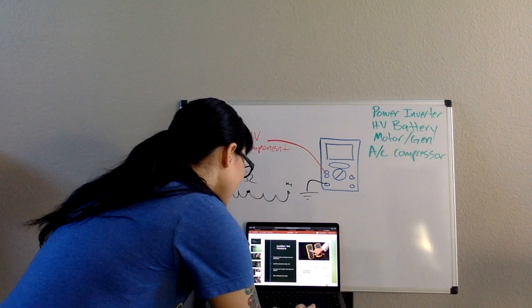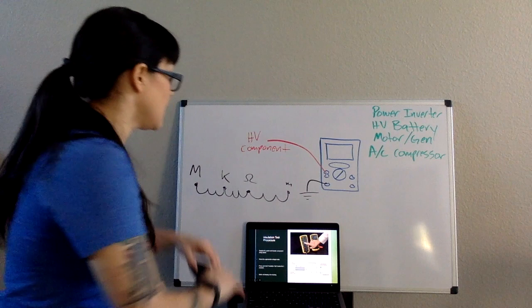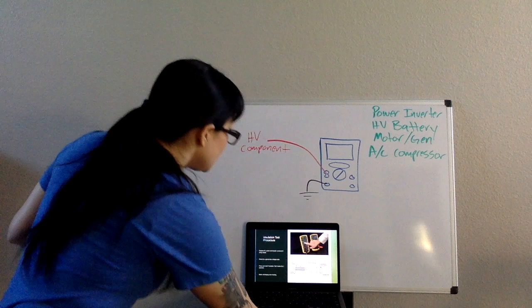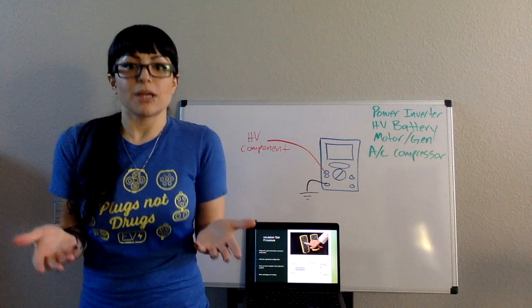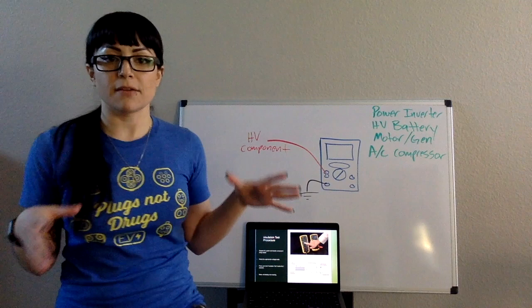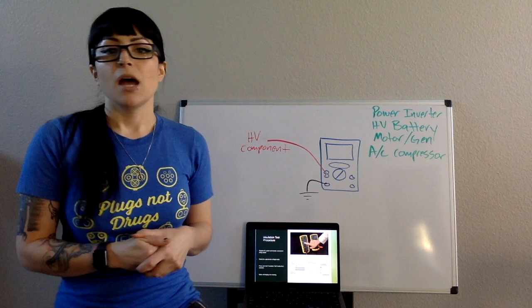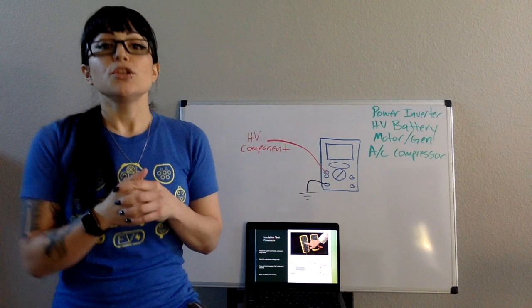Now the procedure itself - first things first, like any other ohm test, you need to isolate what you're working on because now we are changing the power source, and you want to make sure it's safe to work on. So you are going to isolate whatever you're testing. If it's a motor generator, you're going to unbolt the terminals and take that out of the system. Same with power inverters, everything else. You want to make sure you're isolating it from the rest of the system so you're also reading accurately where the problem is.